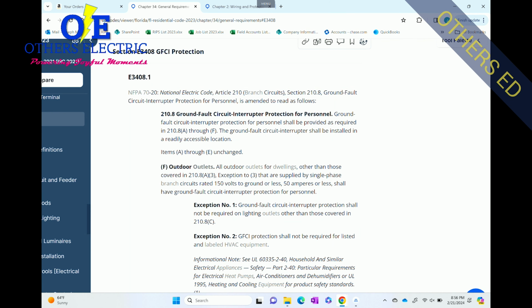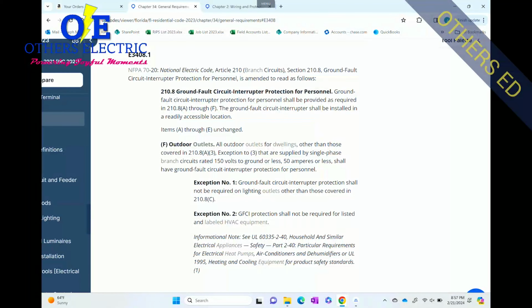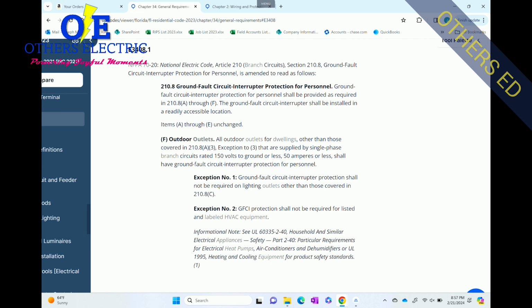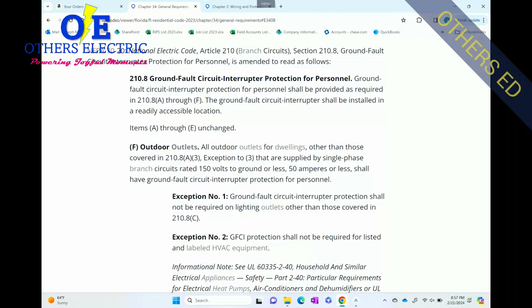Section E3408, GFCI protection. The NFPA 70 National Electrical Code, Article 210, branch circuits, Section 210.8, ground fault circuit interrupter protection for personnel, is amended to read as follows. Ready? Let's read it together. 210.8, ground fault circuit interrupter protection for personnel. Ground fault circuit interrupter protection for personnel shall be provided as required in 210.8 A through F. The ground fault circuit interrupter shall be installed in a readily accessible location. Okay, that didn't change. Items A through E are unchanged. But let's go to F.